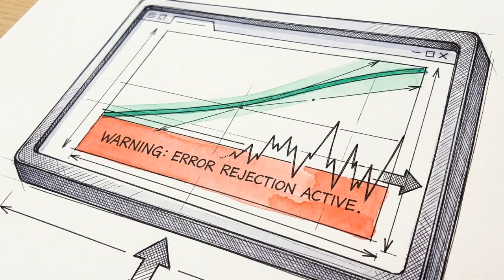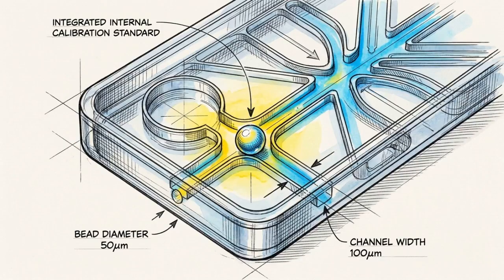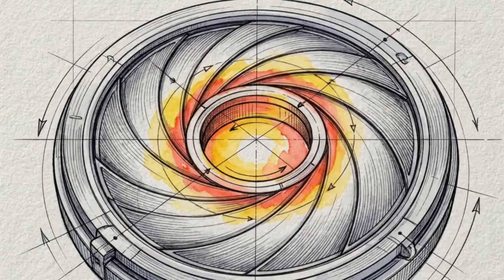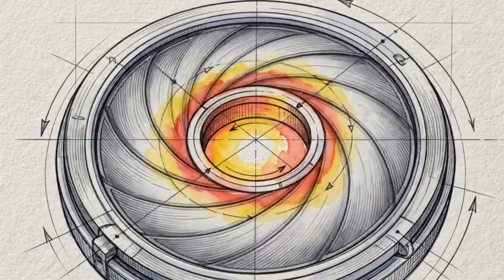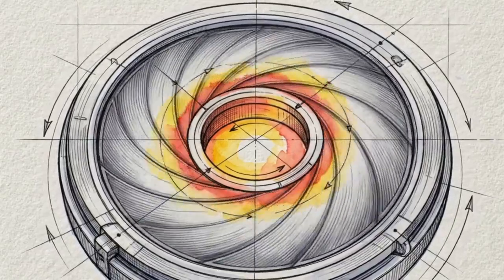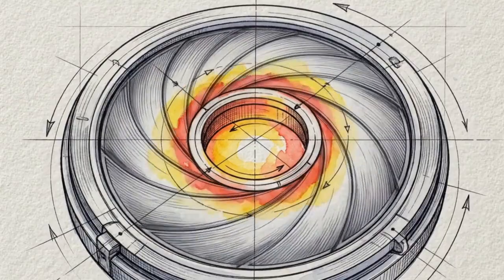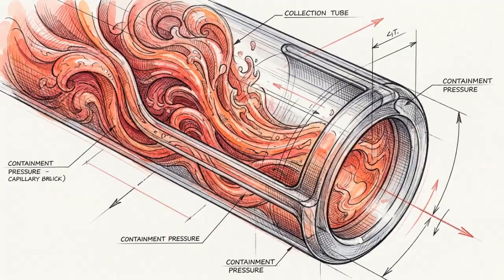Custom firmware is required to instantly track this fluorescence, enforce calibration linearity thresholds, and actively flag out-of-spec runs before they generate false clinical probabilities. To prevent the sensors from drifting over time, the system requires integrated internal calibration standards physically built into the test. The hardware exists for one purpose: locking temperature and light tight enough to feed pristine data into a locked regression model.